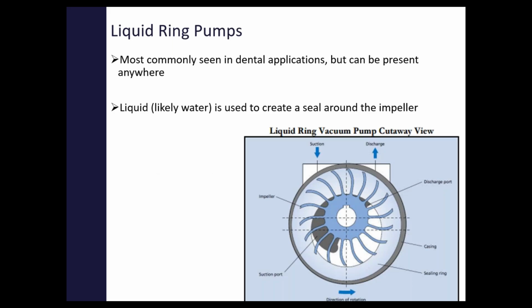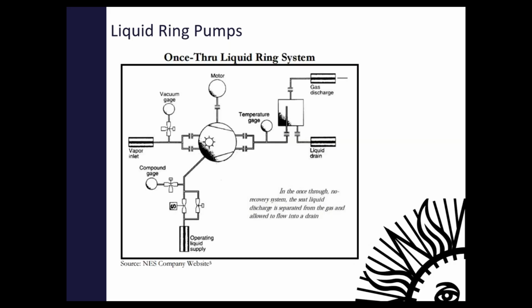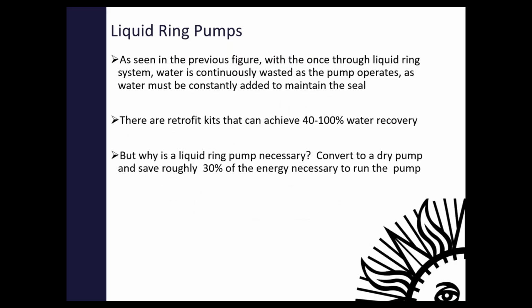Liquid ring pumps, I haven't seen many of these. They use water to maintain the seal around the impeller. So what you can do here is just replace it with a dry pump, and you'll reduce the power consumption and eliminate all your water consumption with that pump. Or you can install a water retrofit kit on the pump.